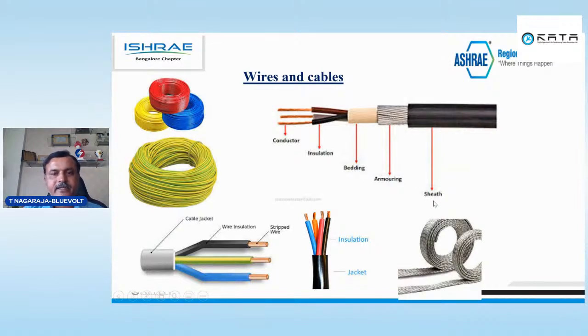So this is a sheath again. This is single core wire for panel wiring. For earthing, we use yellow, with the yellow green band. Same for R, Y, B and neutral. This is a 4-core wire. This is an earthing braided wire. This is also one type of braided wire, only copper braided wire. We can use this for earthing purposes.